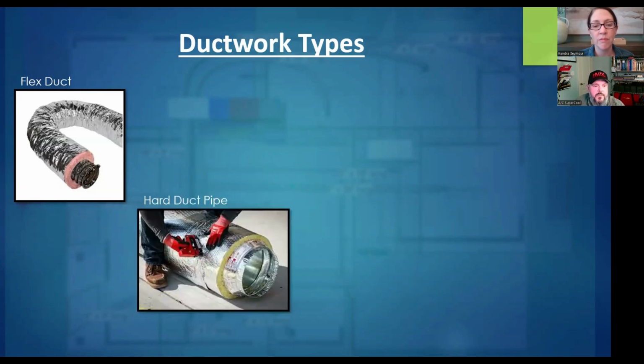Second is hard duct. This is my preferred method. It's rigid, insulated on the outside, leaving a smooth bare metal surface on the inside of the airstream. Given that smooth metal surface, it would be the easiest and most effective choice for cleaning.